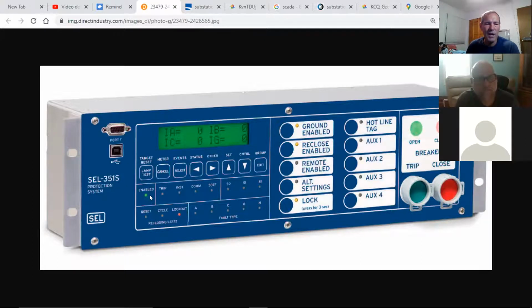Is it working? Is it enabled? Yep, okay. Is it in lockout right now? Yeah, it's in lockout. What kind of trip targets? Did you have a trip? No. Was it an instantaneous trip? No. Do you have communications? No. So there's other stuff you can look at in here.